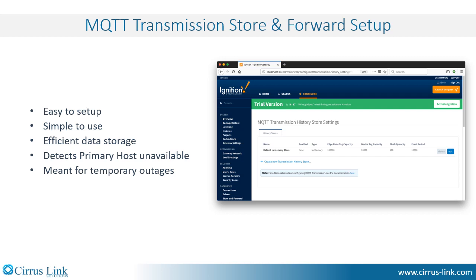MQTT transmission is not designed for large data stores — being offline for weeks or months. It is targeted for temporary outages for hours or days, dependent upon hardware limitations and number of tags.